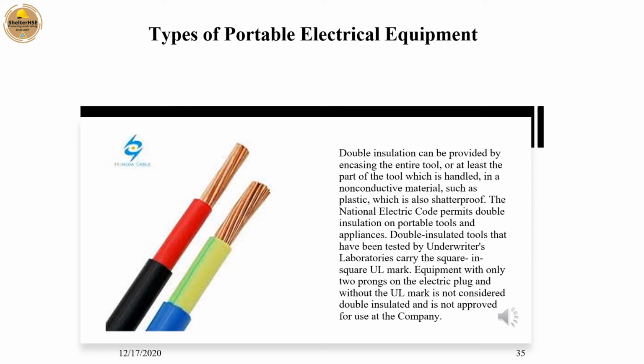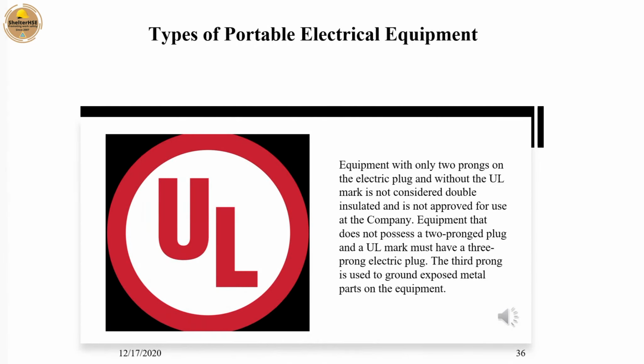Equipment with only 2 prongs on the electric plug and without the UL mark is not considered double insulated and is not approved for use at the company. Equipment that does not possess a 2-prong plug and a UL mark must have a 3-prong electric plug. The 3rd prong is used to ground exposed metal parts on the equipment.